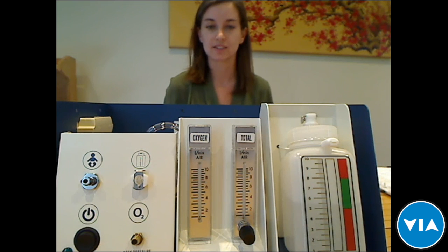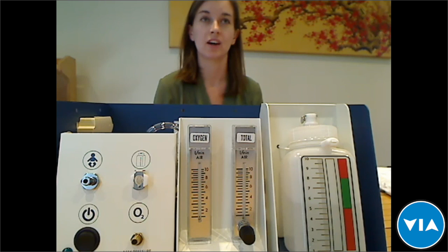So Jocelyn, the first question is just about sterilization of parts and what can be sterilized and what cannot be. Yes, so the tubing, the patient tubing, and the nasal prongs are labeled as single-use only. That means that we cannot ensure that they are clean use after use. However, we understand most hospitals and most clinicians have to and need to clean and reuse. These components are designed to be reusable. They're very durable. But we cannot typically recommend that or label them as multi-use, if that makes sense.